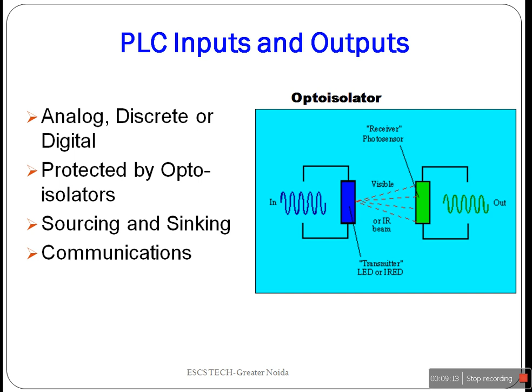The PLC CPU is protected by the opto isolators. This provides electrical isolation from its input and output. The opto isolator uses an LED and a photo sensor to convey the voltage information. This way, if there is a large voltage spike, the PLC and its CPU will not be damaged.